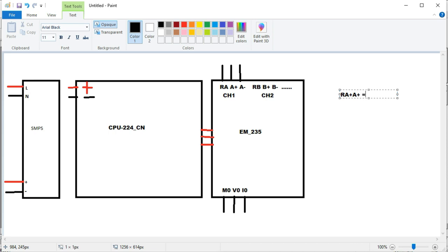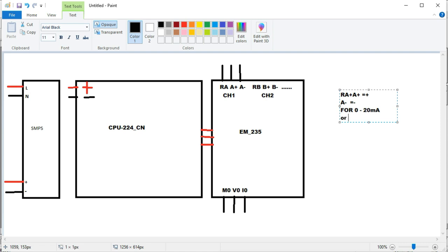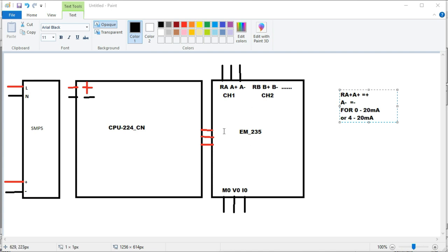When we connect 4 to 20 milliampere or 0 to 20 milliampere signals, A+ is the positive generating input and A- is the negative. For 0 to 20 milliampere, it is A+ positive and A- negative going to M0 and I0. This is our first channel CH1, and this is the second channel. The third and fourth channels are also within the EM 235 extension module. Four inputs and one output are available.